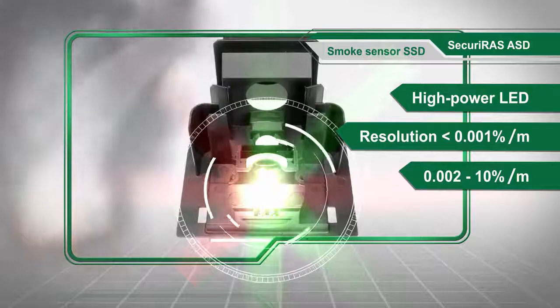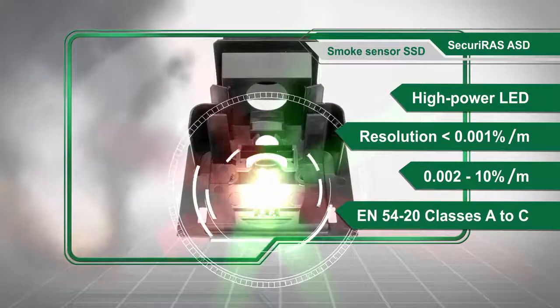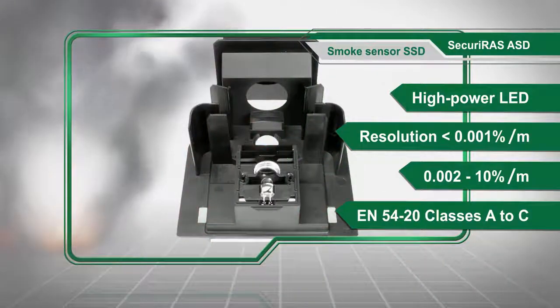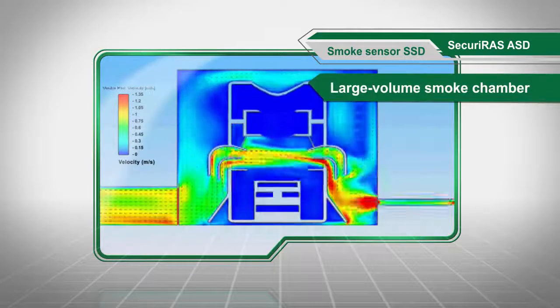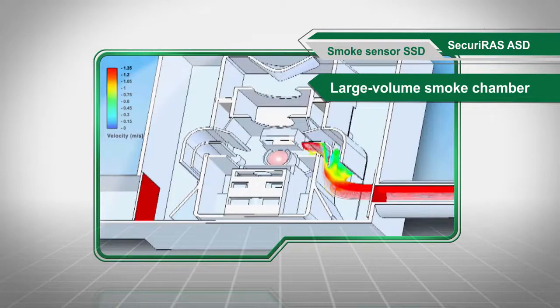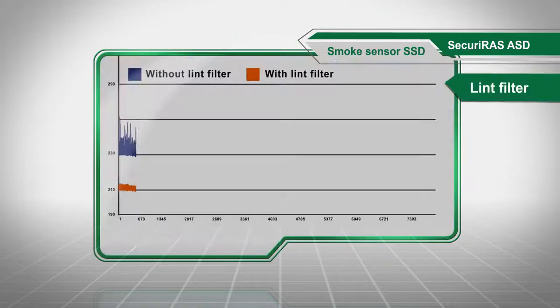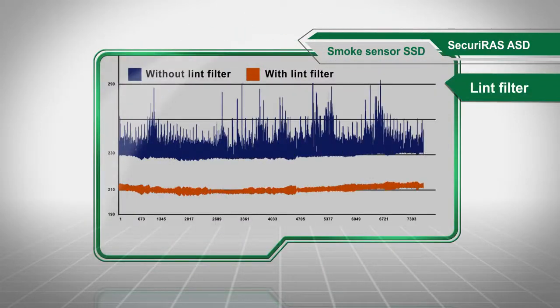It can be used in applications in classes A to C according to DIN EN 54-20. Using state-of-the-art simulation technologies, the large volume smoke chamber on the SSD smoke sensor is designed to achieve the highest possible sensitivity while maintaining long-term stability. The patented Lint filter allows individual disruptive factors to be simply ignored.